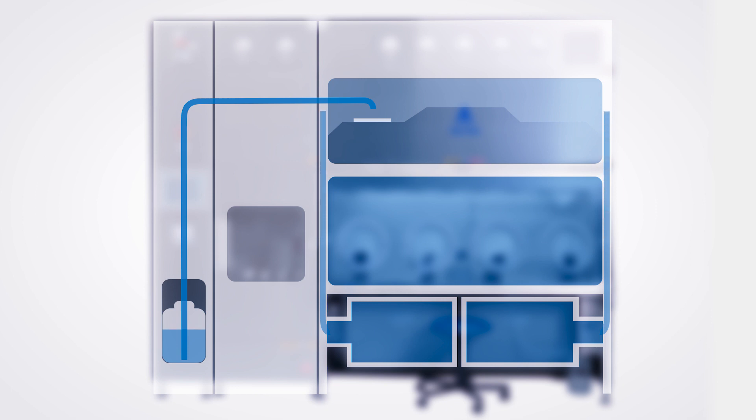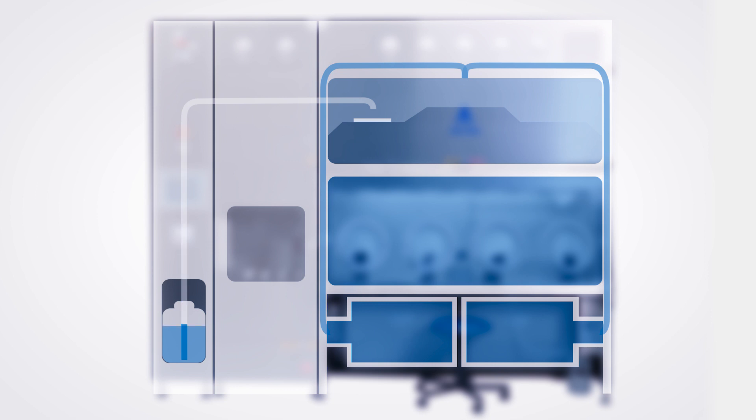Hydrogen peroxide is the most widely used and accepted agent for isolator decontamination. Liquid hydrogen peroxide is pumped from the dosing station to the evaporator, where the liquid is converted into steam by flash evaporation. The steam is taken by the blower and pushed through the HEPA filter into the main chamber, where the hydrogen peroxide is distributed into the load. During the decontamination phase, hydrogen peroxide concentration remains constant, circulated in a closed circuit at low air velocity.